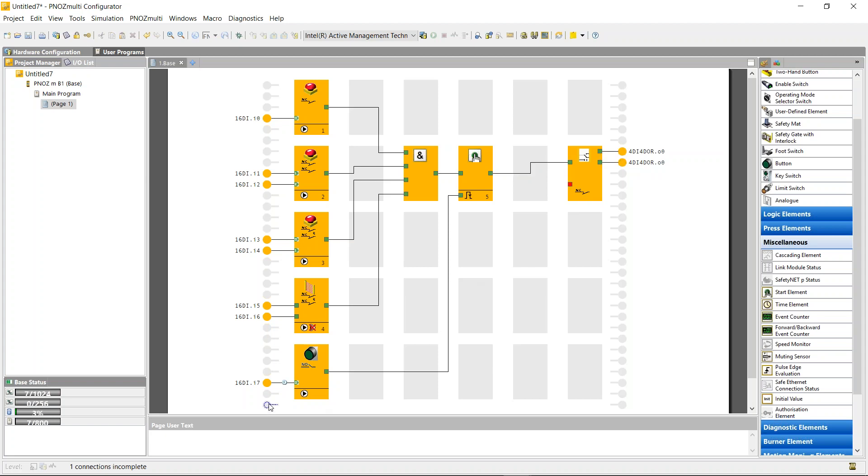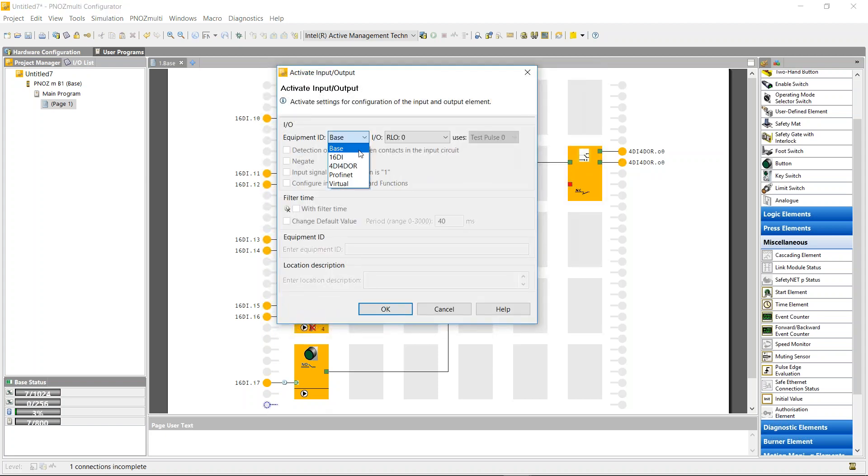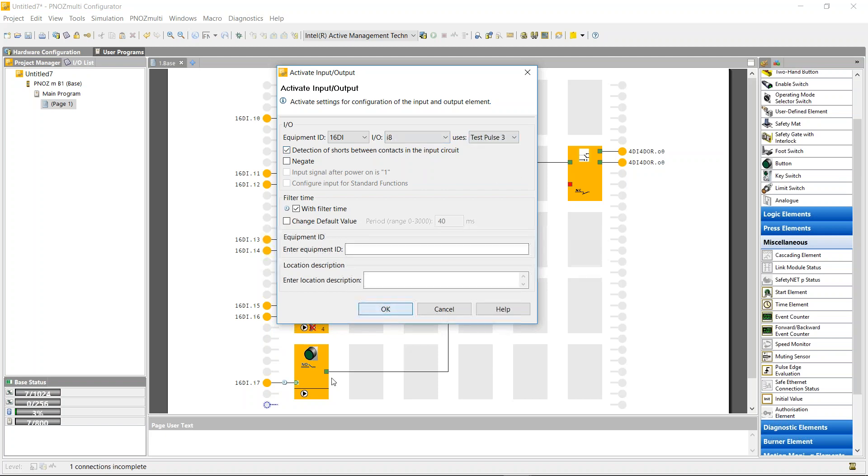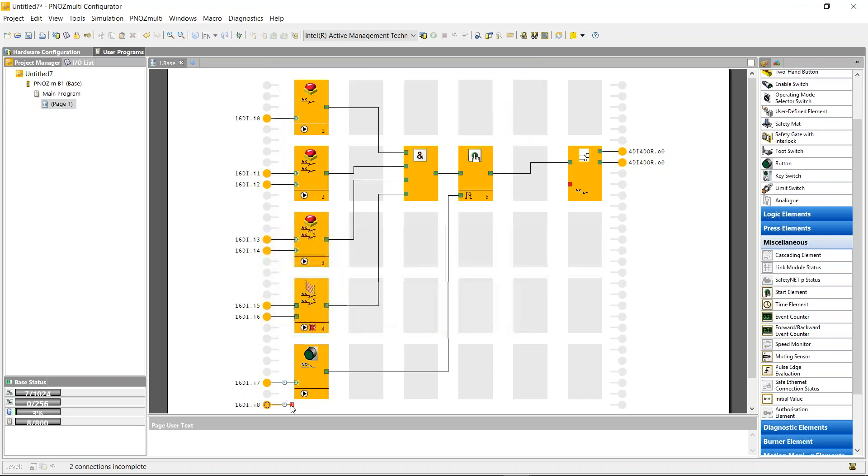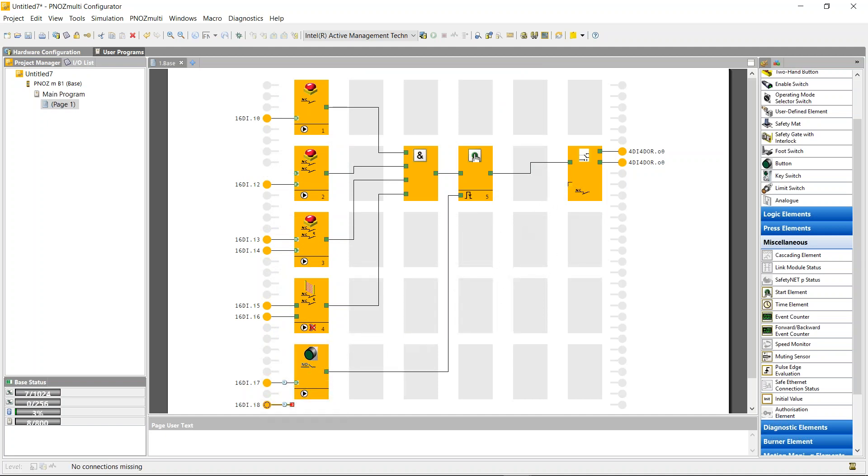If I use a test pulse through that, I can just say it's in the 16 digital input at I8 and use test pulse 3. So I'm now constantly monitoring the normally closed part of the contactor. I've now built a circuit with four inputs, manual restart, and feedback.